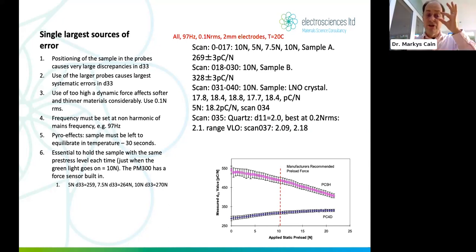And it's essential to hold the sample with the same pre-stress every time. So this is really important. The PM300, this instrument that most of you will probably have, or something like that, has got a force sensor built in, but the previous ones didn't, okay? So you don't necessarily know the preload unless you put some load cell in there, which I've done, I'll show you in a minute or two. And then you just sort of screw the screw down one turn and say, one turn is my standard method, and that's exactly always the same.